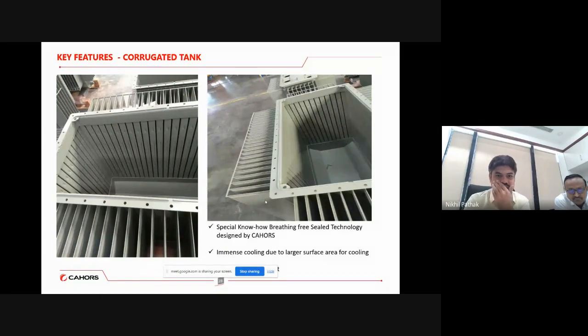Now this is the inner view of the corrugated tank. So now you can see, instead of a 3 inch opening pipe and multiple radiators for cooling, every fin of the transformer is open from inside, so that multiple cooling ducts with a larger surface area are given for the cooling of the transformer. So at any given point of time, the temperature rise values are always within the limits, because the oil remains on the air surface of the transformer, and it gives continuous support for the cooling.